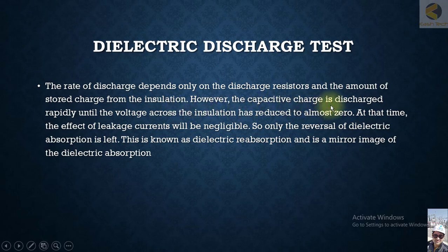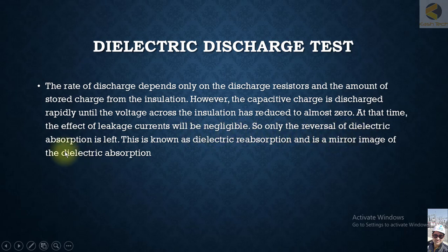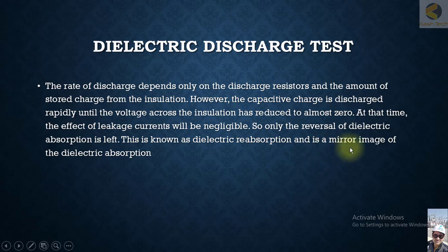The capacitive charges discharge rapidly until the voltage across the insulation has reduced to almost zero. At that point, the effect of leakage current will be negligible, so only the reversal of dielectric absorption is left. This is known as dielectric reabsorption, and it is a mirror image of dielectric absorption.